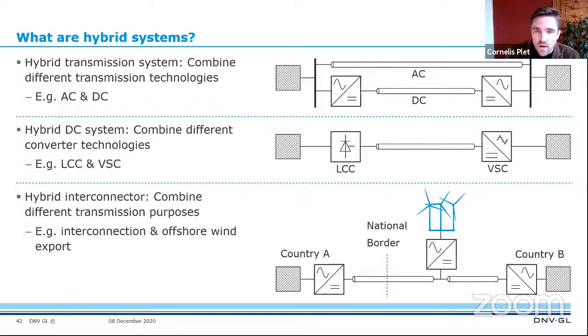In some specific cases, this isn't actually a problem. For example, where power flow goes predominantly in one direction, you could apply this type of hybrid HVDC system. One example is the Wudongde project in China, currently in commissioning. This is actually a three-terminal project, of which one terminal is 8 gigawatts—a rating not yet available in VSC, so it has to be LCC. The other terminals are 5 and 3 gigawatts at 800 kV. Time will tell how successful this system is.